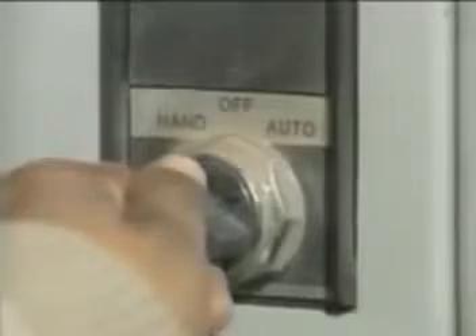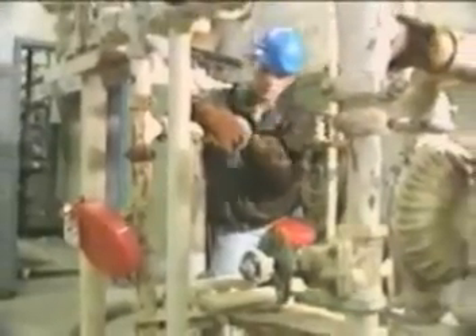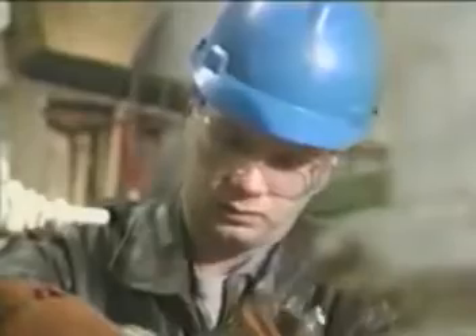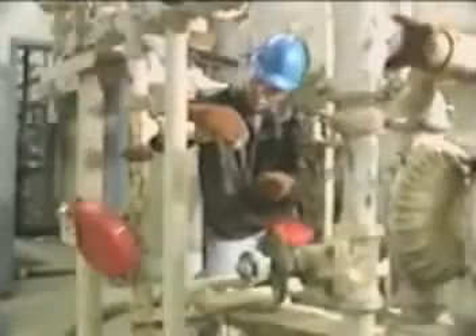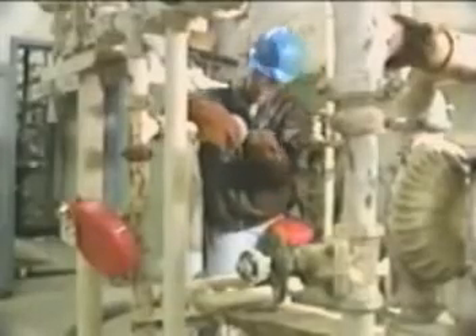So press all start buttons or other activating controls, then return them to the off position. This will prevent the equipment from starting by itself when energy is restored. You are now ready to perform the work. If lockout tagout steps are performed correctly, everything should be fine. However, always be conscious of the possibility of accidental restarting or activation of the equipment while you are servicing it.